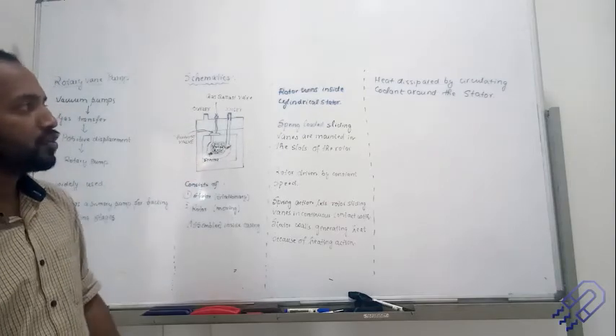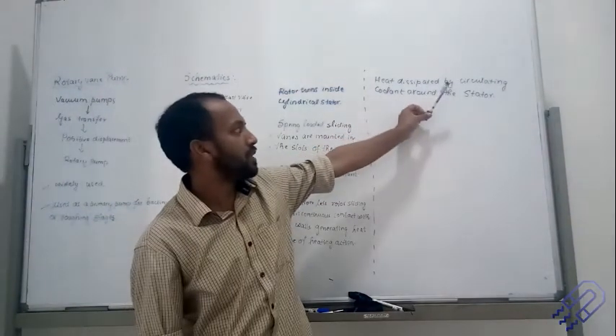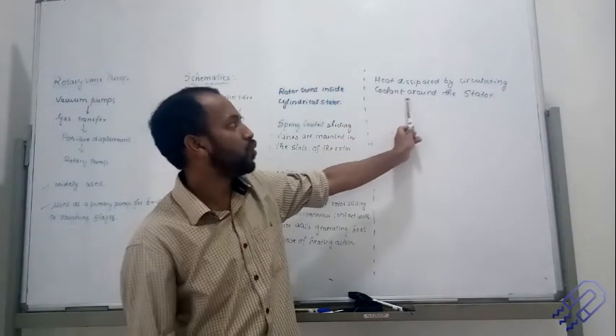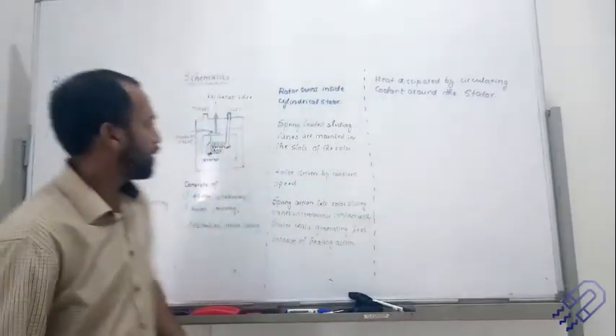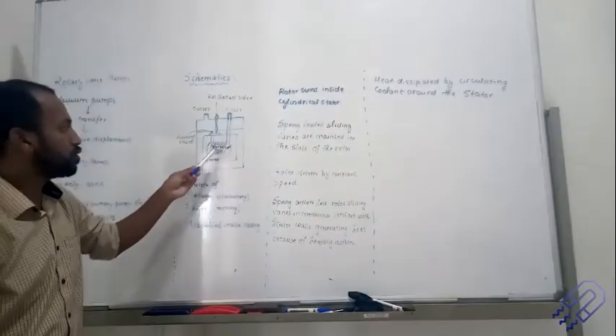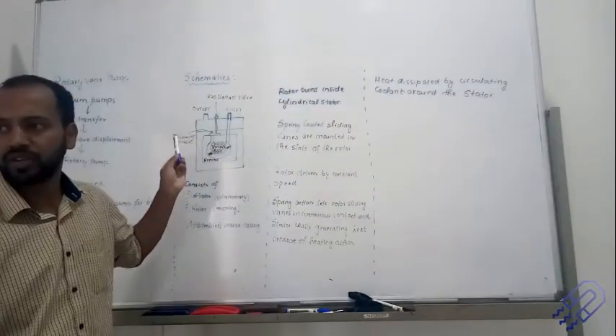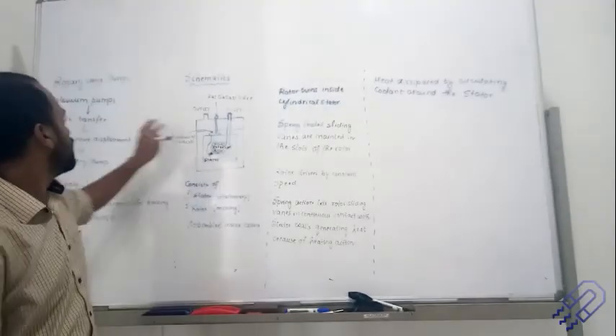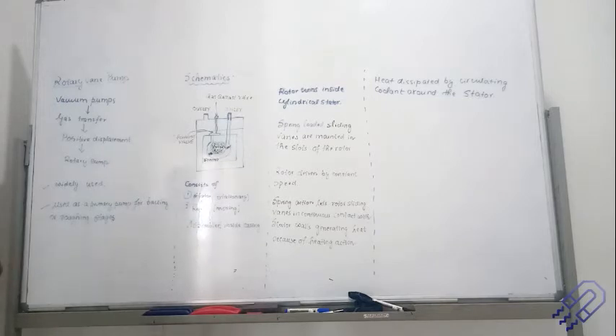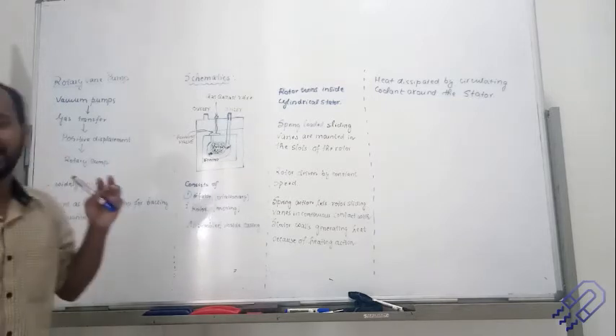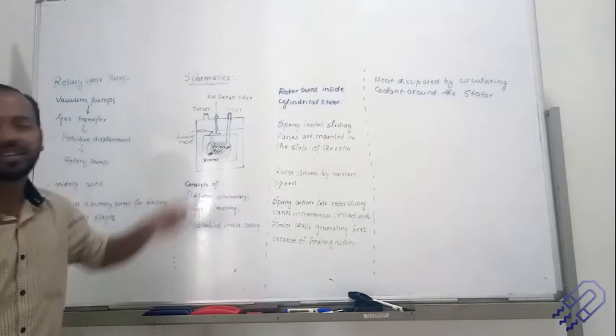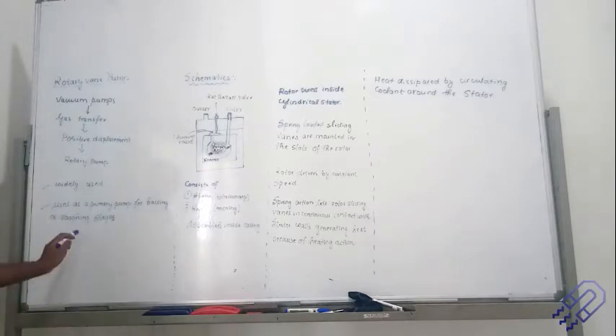The heat is dissipated by circulating coolant around the stator. In a normal rotary pump, some oil is also used. Because the rotor is not rotating at a very high speed, it does not generate too much heat — which is also why we call it a roughing pump.